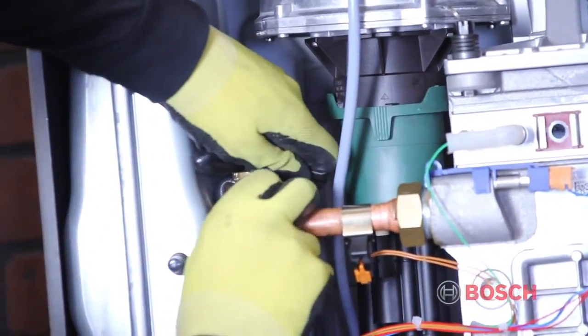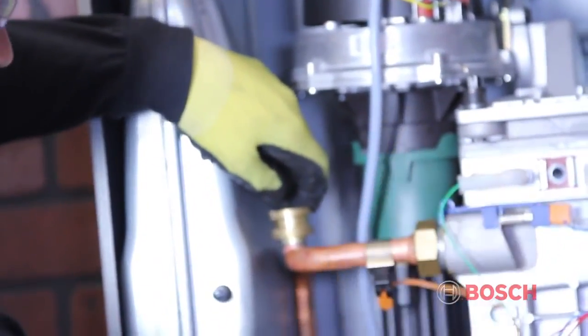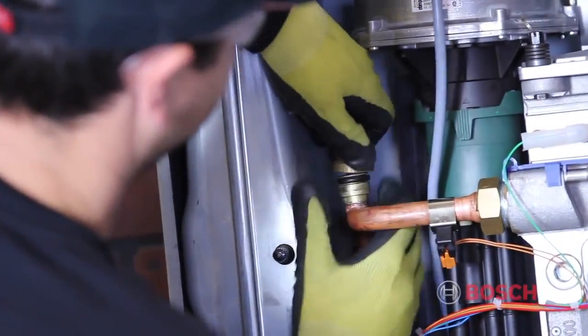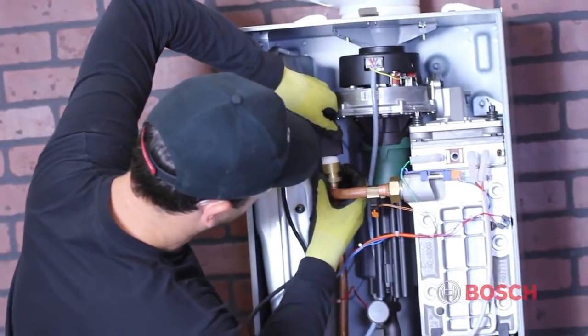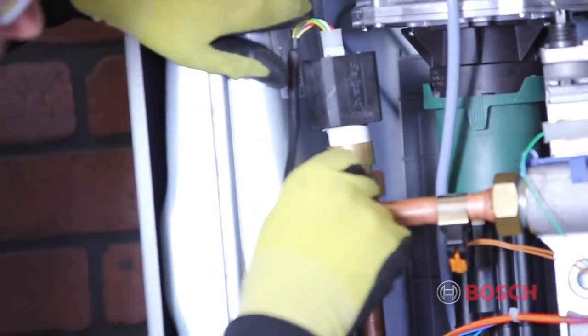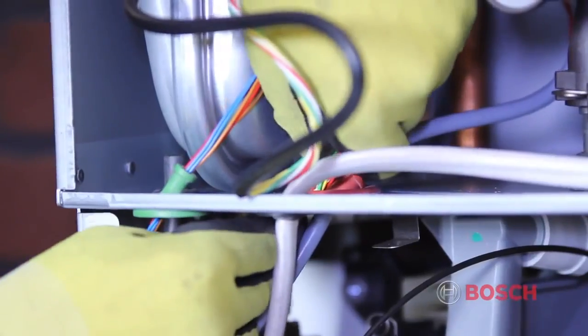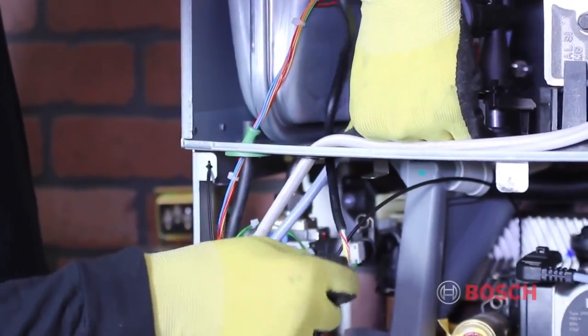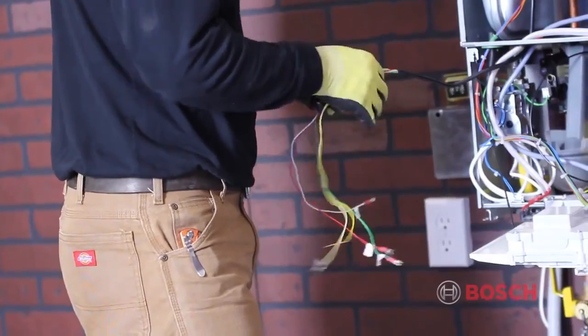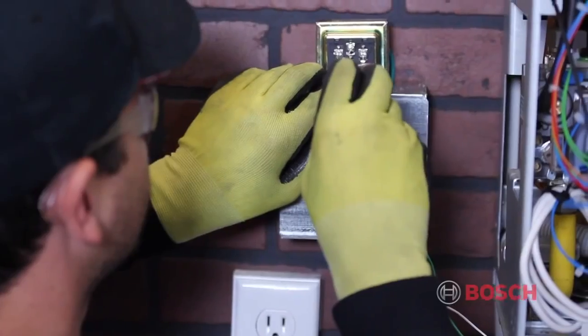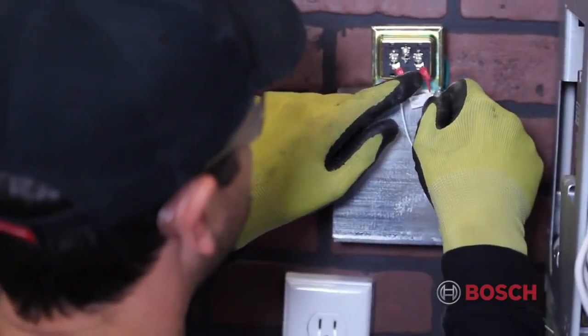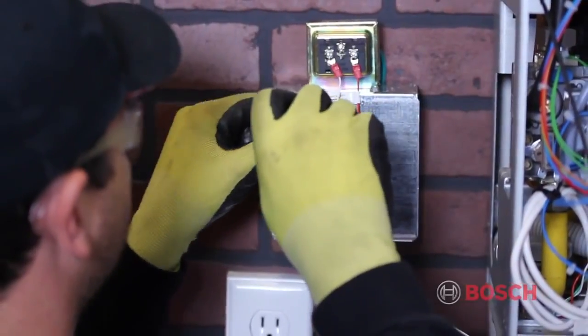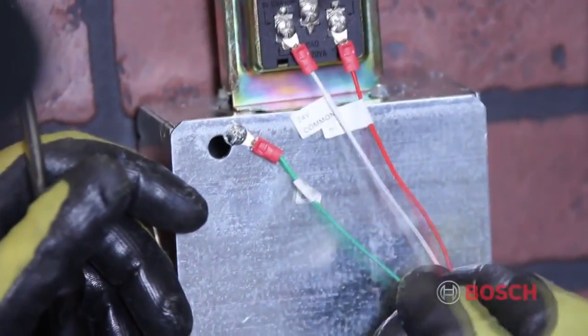To connect the low water cutoff, remove the pipe clip from the plug in the supply pipe. Once removed, the plug will pull straight up. Connect the low water cutoff to the adapter provided and push back into place and reinstall the clip. Run the wire down to the grommet with a fan wire running through it. Poke a hole in the grommet and push the wires through. Once pushed through, connect the power wires to the transformer. Make sure to connect to a solid earth ground.